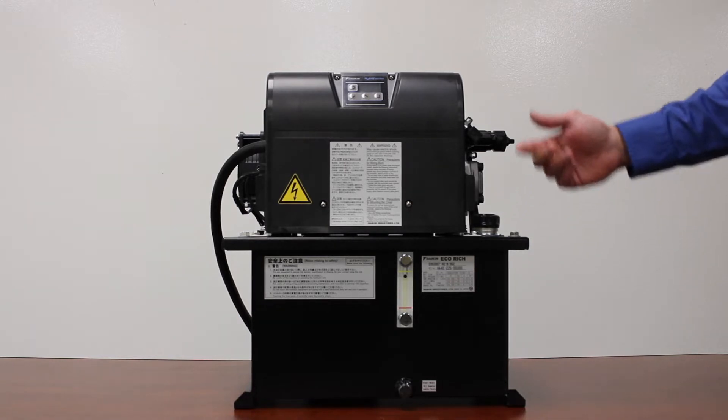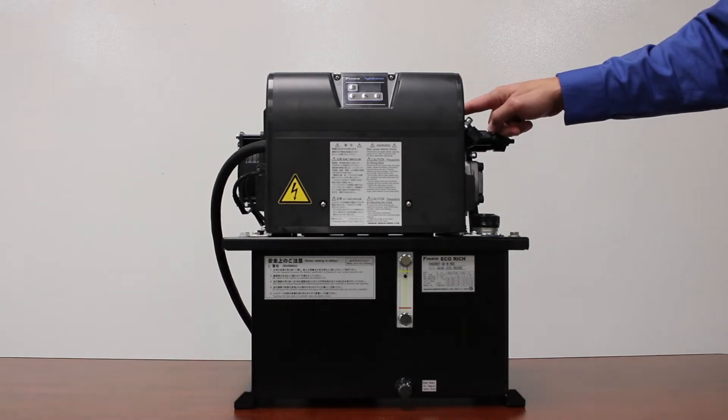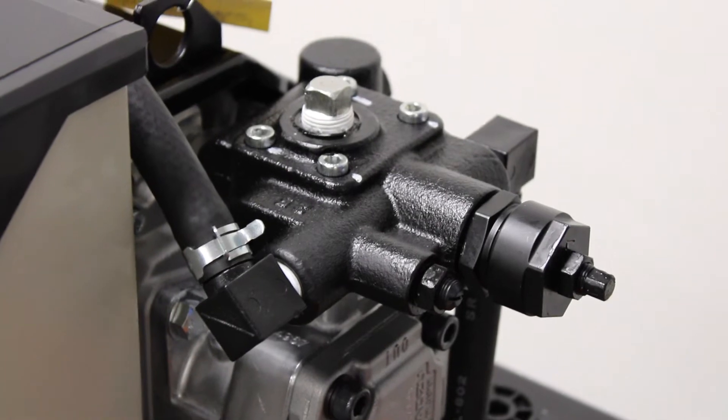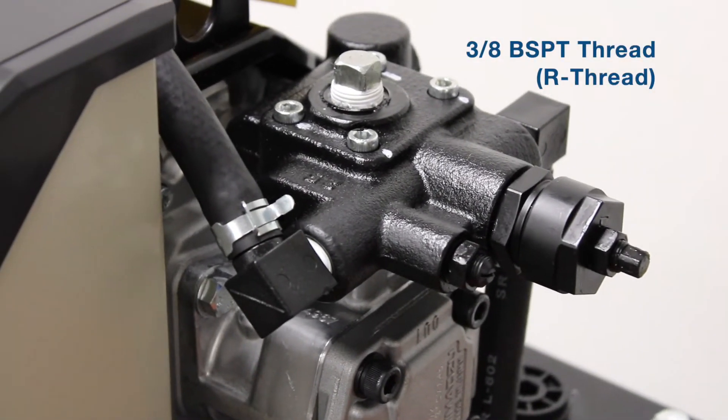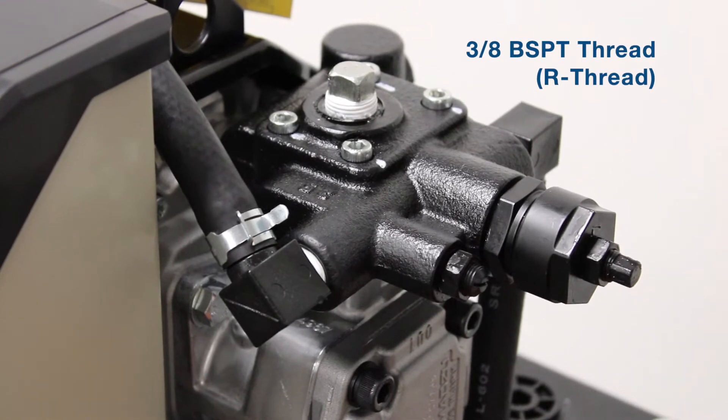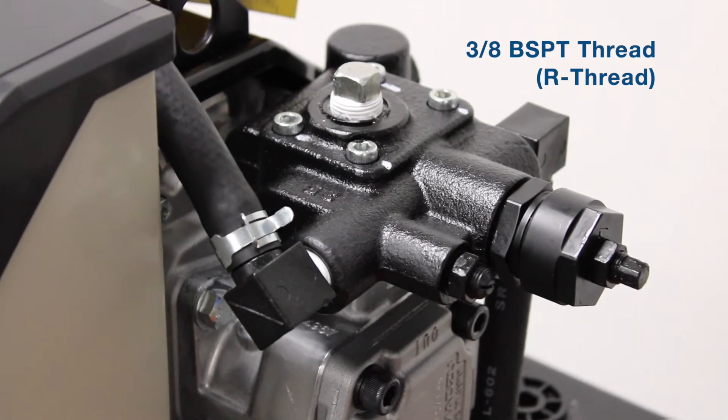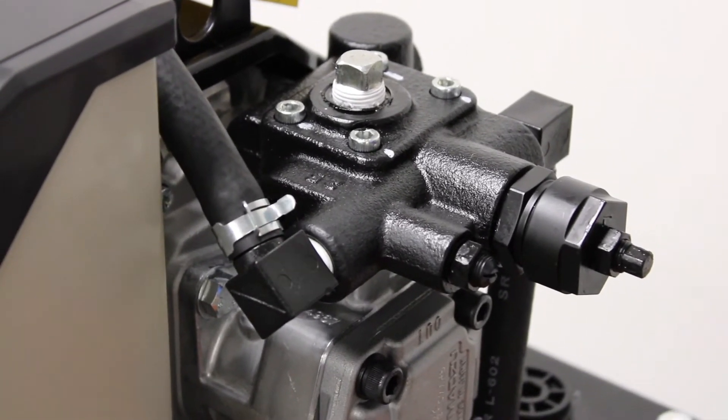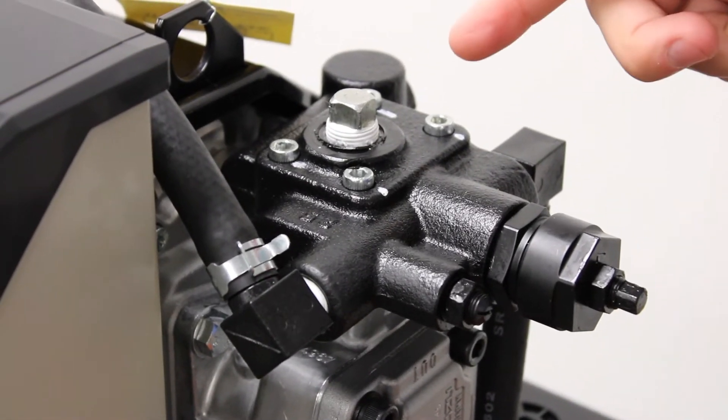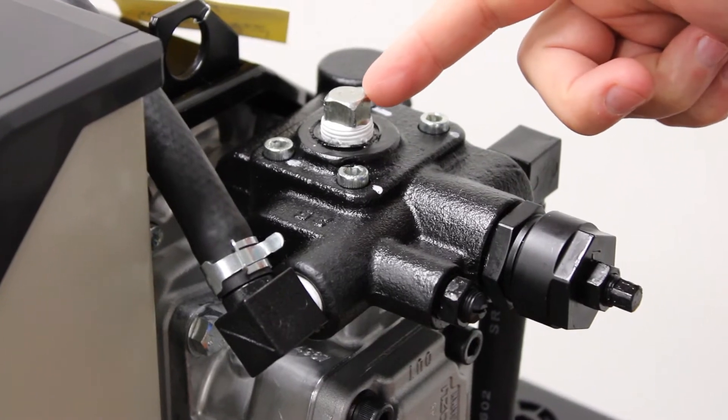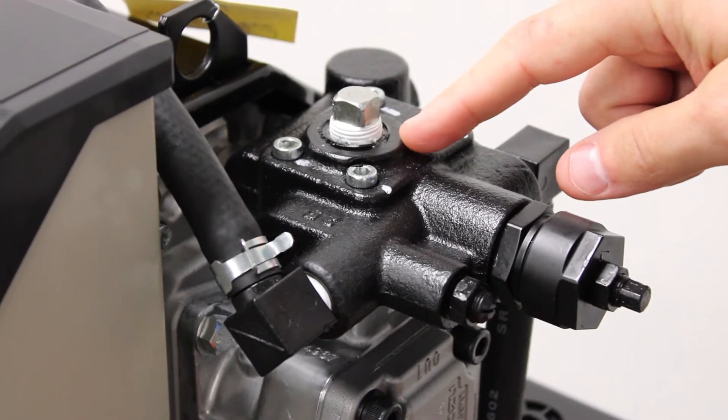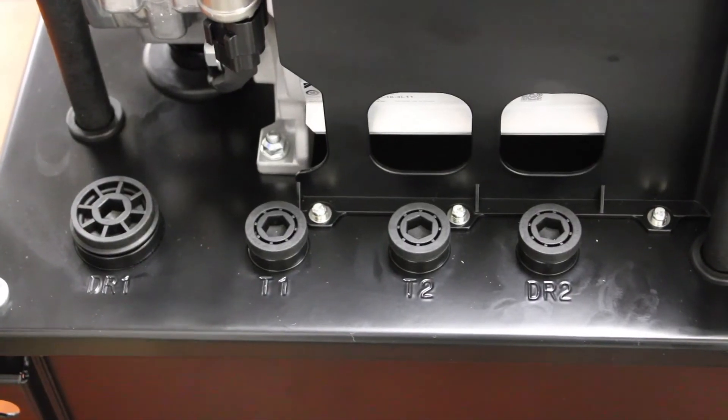Once we've filled up our tank with oil through the fill, we'll connect our pressure and return lines to our application. The pressure port is right here on the top. This is a three-eighths BSPT thread, also known as British Standard Pipe Taper thread, commonly referred to as an R thread. That's important because we're going to be talking about 1000 psi, so we want to make sure we have the right fitting and we'll connect right off the head of the pump.